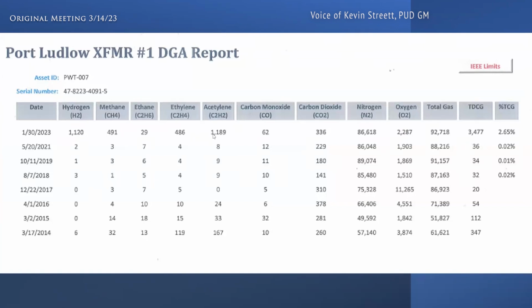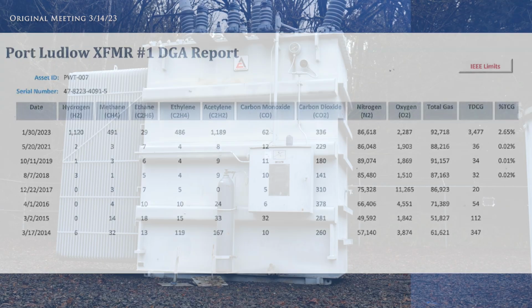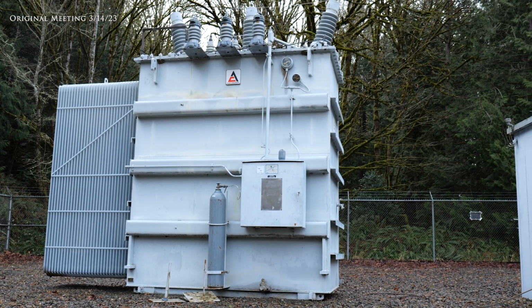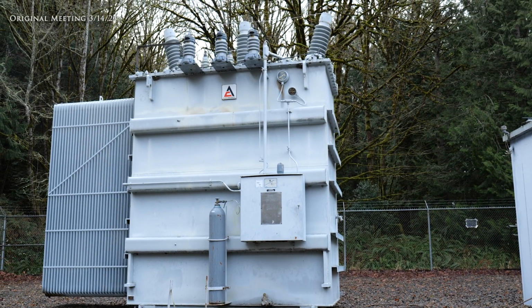Based on this, we're very comfortable that our fault was due to a winding failure, which means our core steel is good. So that's one of the reasons we're recommending to send it off to be rebuilt. They will reuse the core steel, they will reuse the tank, and they will basically rewrap the core steel with the copper so it looks very similar, and then move that transformer forward. That was a real quick understanding of the transformer.